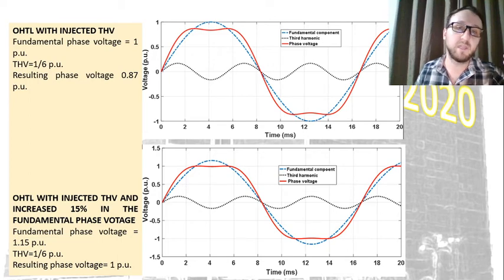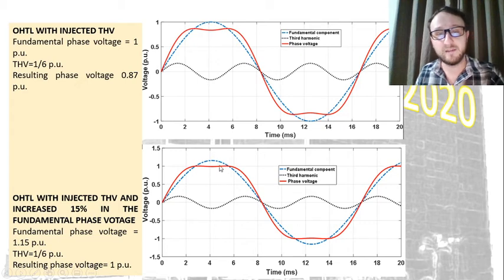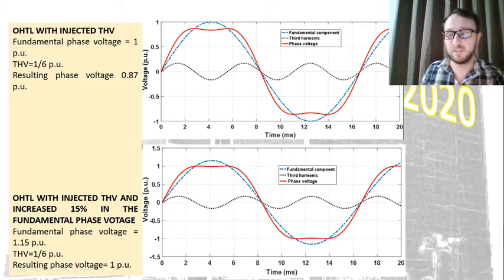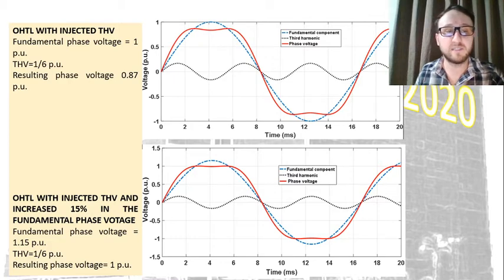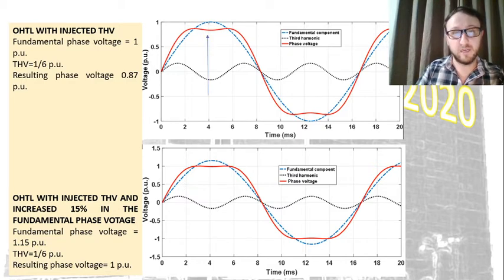So we reduce the peak of the fundamental wave, and once this is done, we can increase the amplitude at the receiving end, up to 15%, and we will have this red curve, the resulting phase voltage, up to 1 pu value. So we can increase 15%, and the best value for the amplitude of the third harmonic voltage generator is 1/6 pu. Here we have the amplitude, and here when we increase by this value.